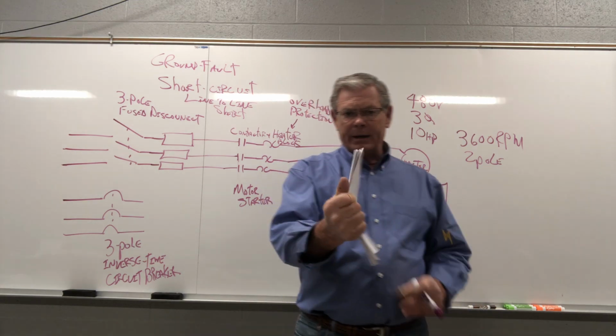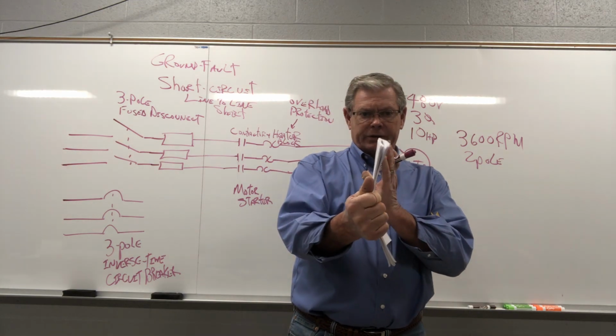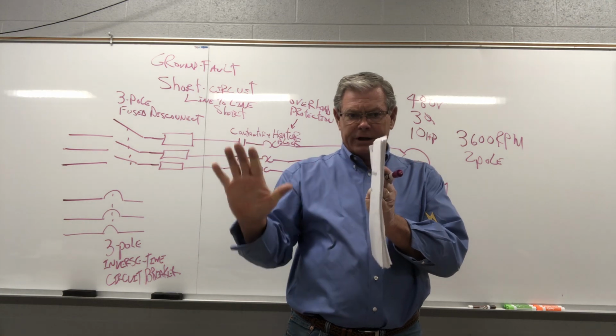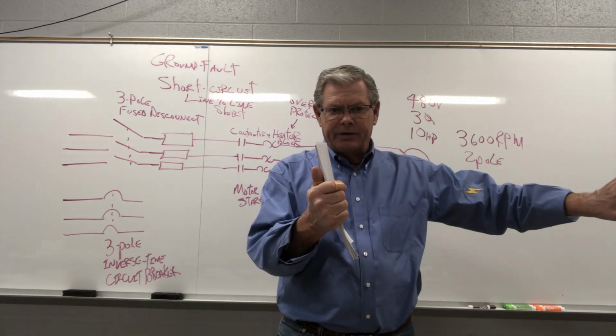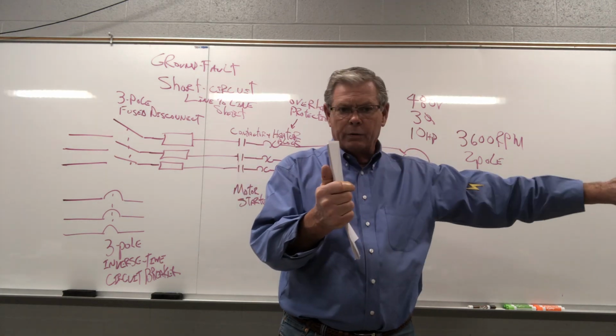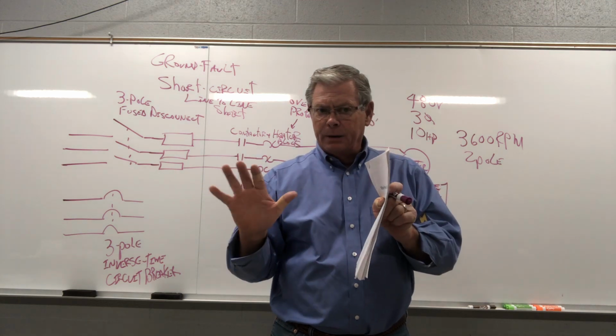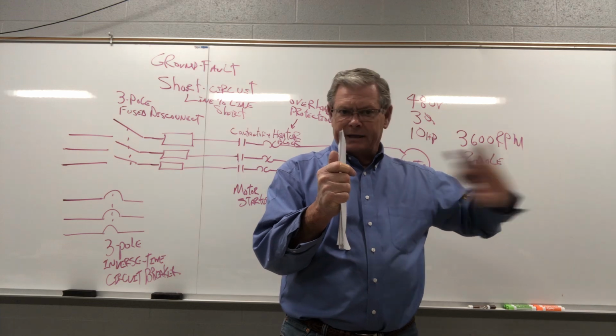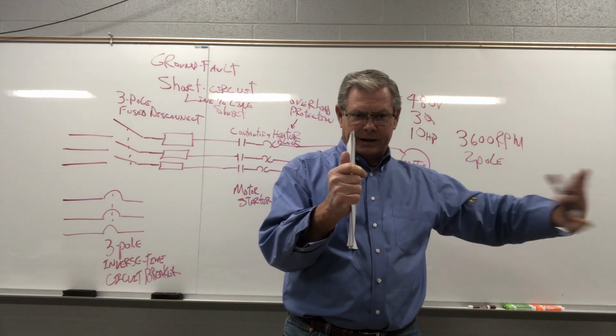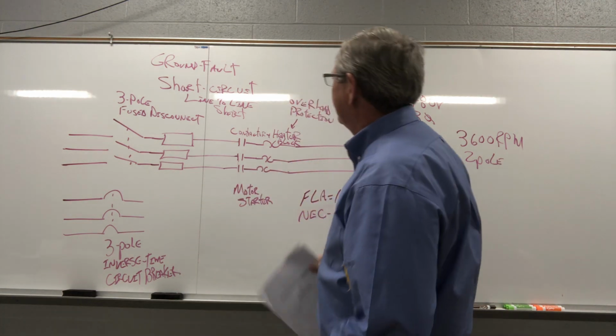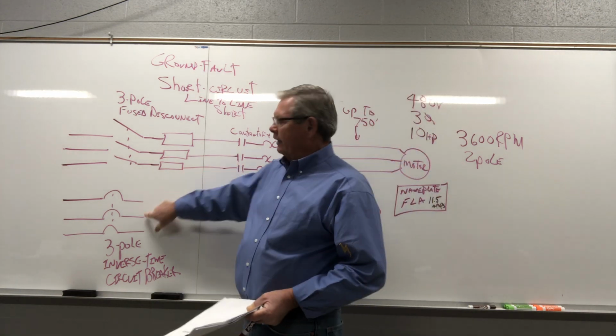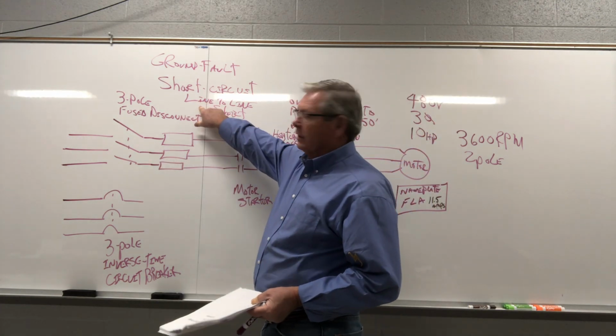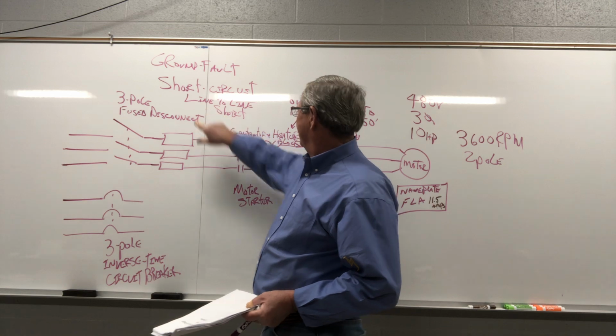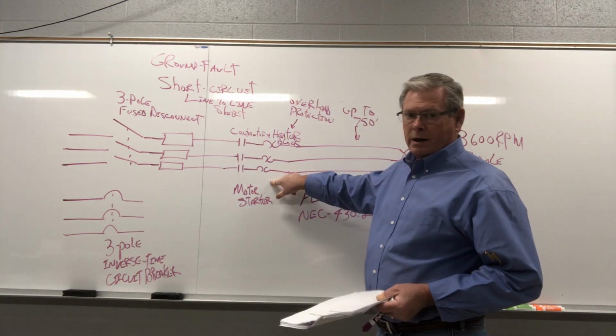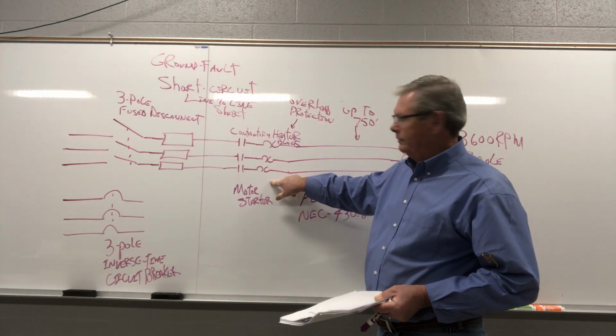So Tom Henry says the code book's got a wall in it, okay? Over here's motors, and over here's everything else. So what we're getting ready to talk about only applies to motors. You calculate fuses and breakers and wire size totally different over here for everything else, okay? So your fuses and/or circuit breaker gives us line-to-line short and ground fault protection. Our overload block gives us motor overload protection, okay?